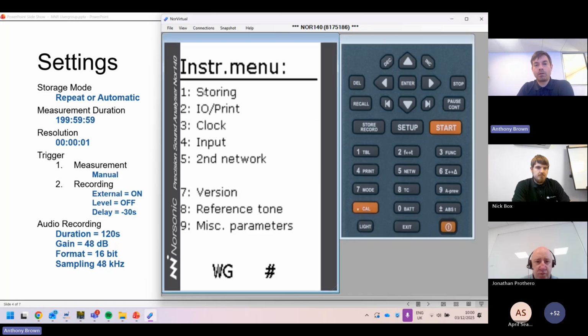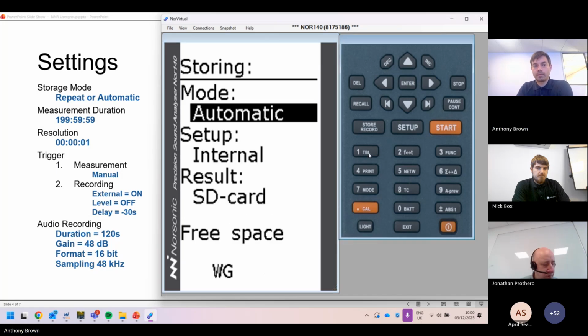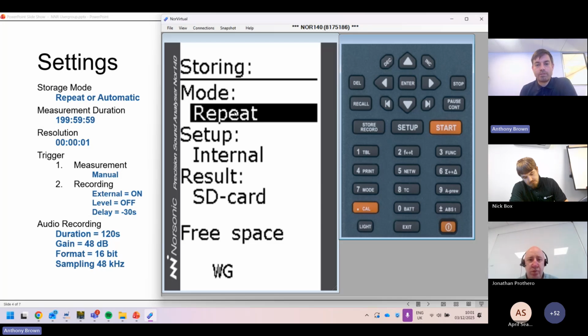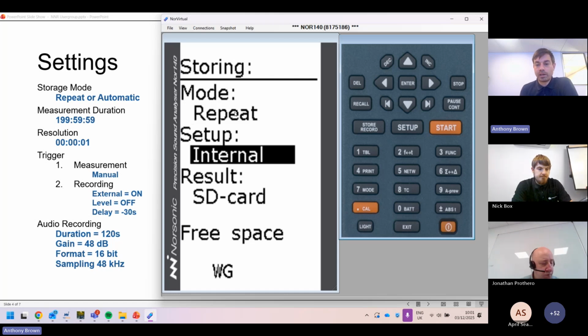So we're in the instrument menu, which was number 1 of the setup menu, and then it's number 1 for storing. What we're going to do now is set up our meter so it runs for a whole week. So long as this top mode is set to automatic, it will run for a whole week. If you want to run the meter for 2 weeks, or indefinitely until you pick it up, then you can change this to a setting called repeat. That's done by pressing the inc or the dec key, and it will change the value in this menu. You just need to make sure that your cursor is hovered over that option. So I've got mine set to repeat. You can do automatic, it doesn't matter. It only depends on your circumstances.